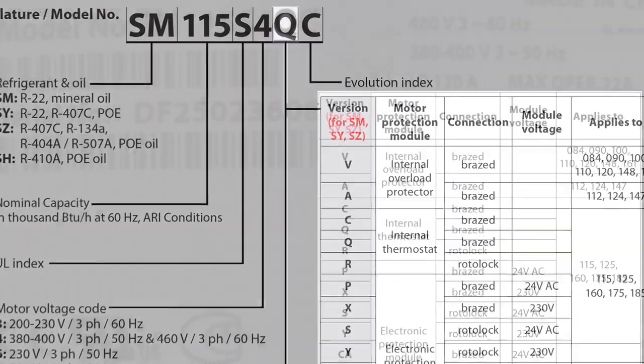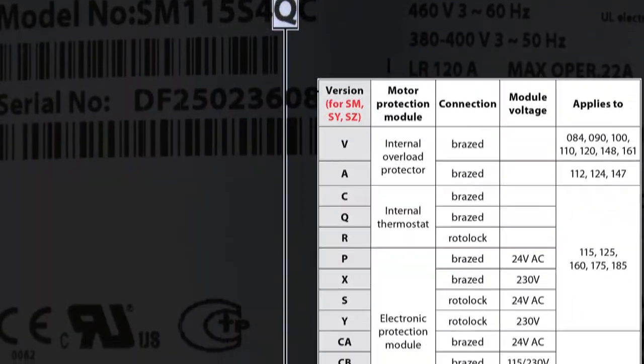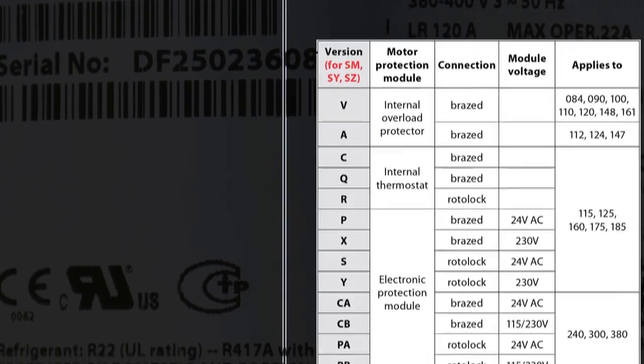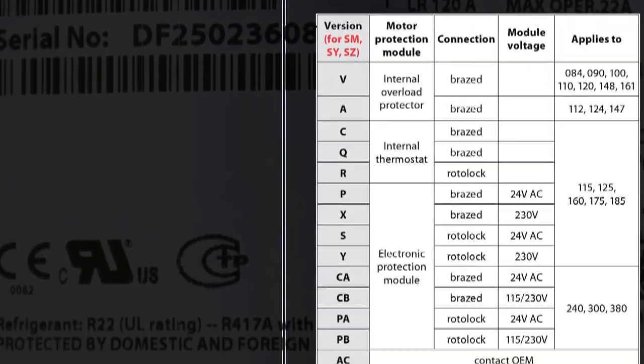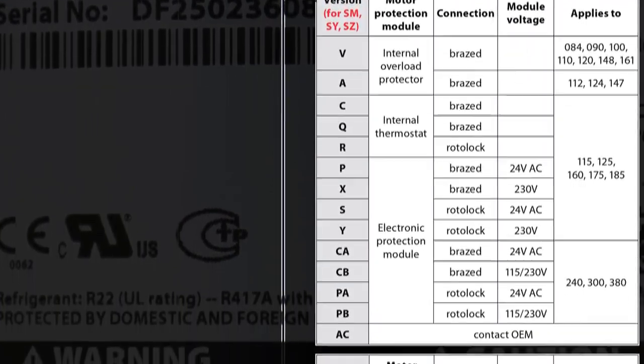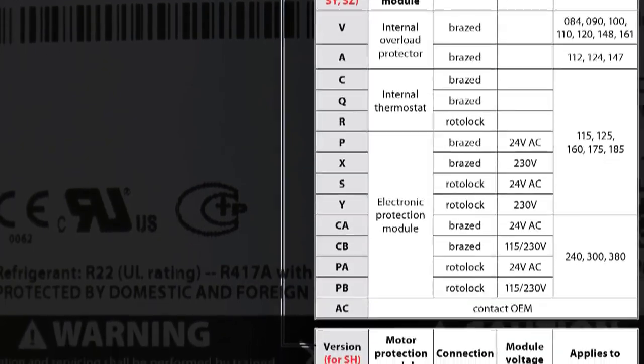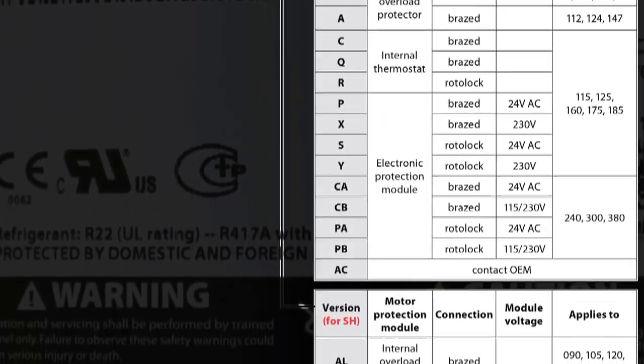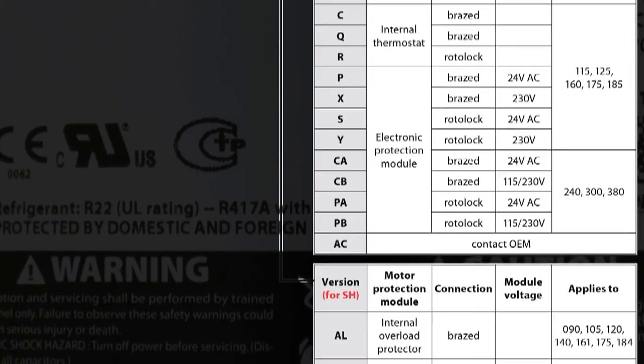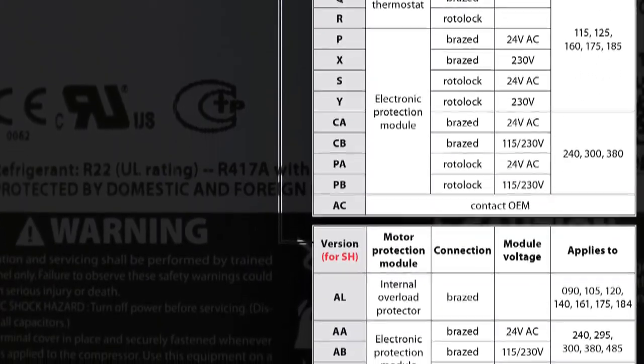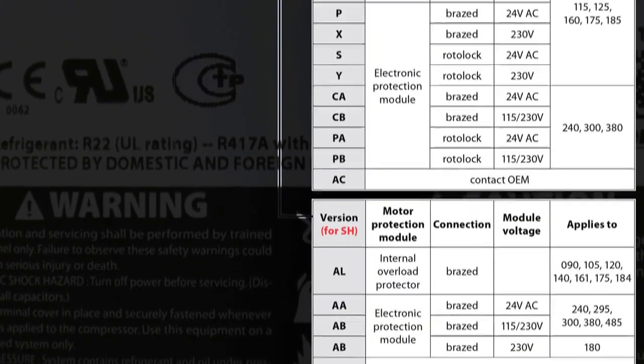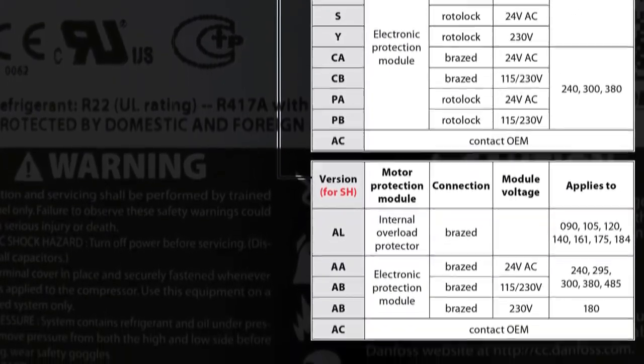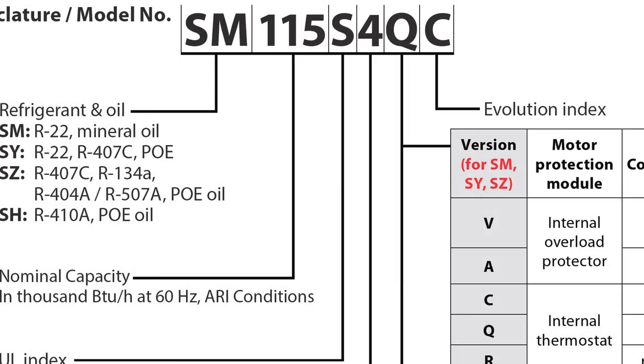The eighth and possibly ninth digits signify the version index, which specifies the types of motor protection and connection used. The motor protection type will be an internal overload protector, an internal thermostat, or an electronic protection module. The connection type will either be brazed or rotolock fittings. Certain features in the version index will only apply to compressors of a specific capacity or range of capacities.